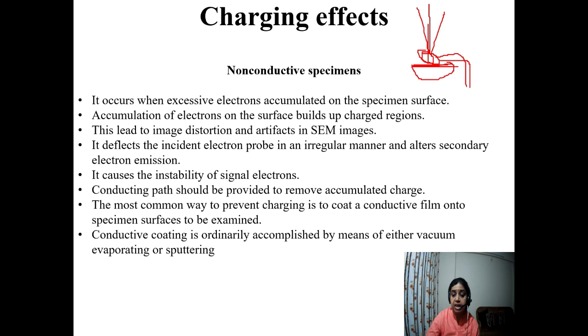We can't take any kind of information due to charging. Just now I mentioned, if electrons are accumulated over here, electrons are coming, so it will just deflect it. We can't see any information, just a bright spot. Whenever you have a bright spot, it means your sample is very non-conductive and it is a charging effect. It is not a feature of your sample.